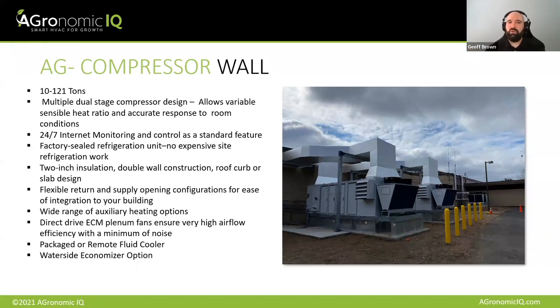So we're able to turn those compressor circuits on or off, and at different stages, again, to very tightly tailor the work that we're applying to the room demands. The stage of your plants, if you're in veg, whether those plants are small, and as you know, following them through the flower cycle, through sort of week 6 of flower, where your dehumidification demand is absolute peak, and then back again as that flower cycle ends, you start cooling things off, drying things down. We can tailor our capacity to it very, very tightly.